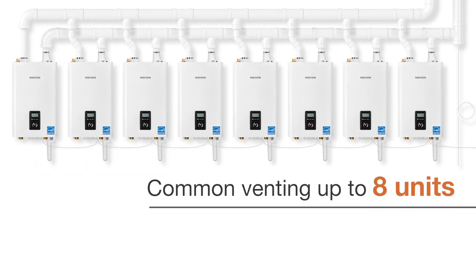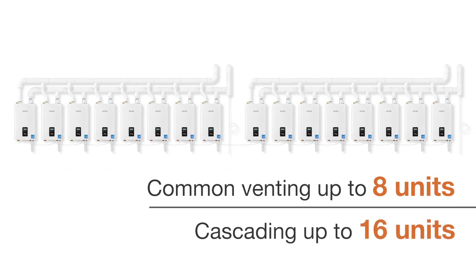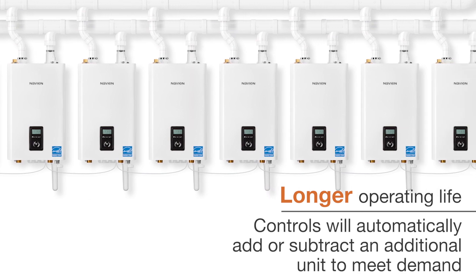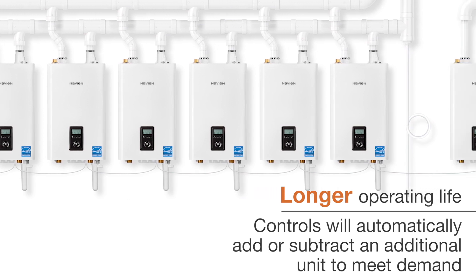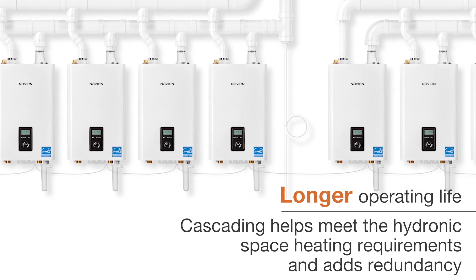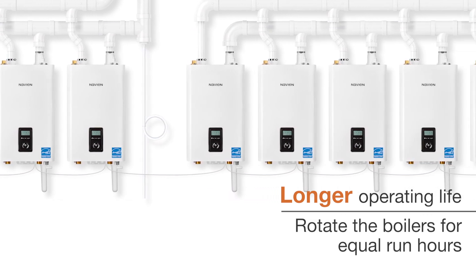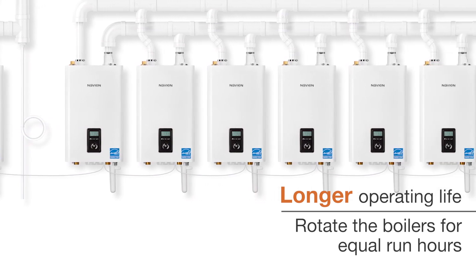With common venting up to 8 units and cascading up to 16 units, the Navien cascading system is able to provide a wide range of heating output. When a unit reaches a preset capacity, the controls will automatically add or subtract an additional unit to meet demand. This provides the benefit of the combined turndown ratio of all units — a 4-unit cascade can provide a turndown ratio of up to 60 to 1. The system is also designed to rotate the boilers for equal run hours, extending the operating life of each unit.